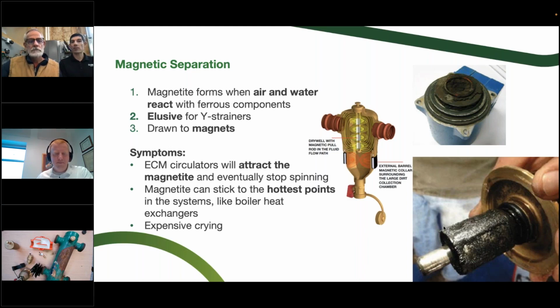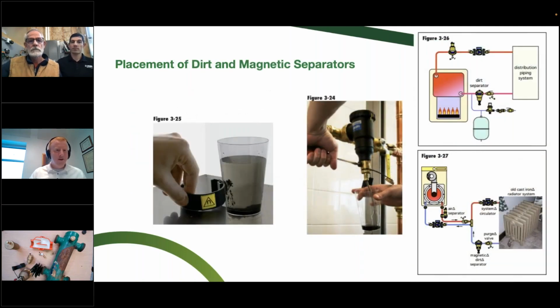So we need to have a better magnet to catch that magnetite first, to protect the pumps and to protect the magnetite from cooking on the hottest points of the system, like a boiler heat exchanger. I think the other thing to think about too is recognizing that it is a magnetite issue. I talk to a lot of contractors where they see a circulator fail. Do they really take it apart to the point where they can figure out that it was magnetite? Oh, heck no, they don't do that. This thing's a piece of junk. They rip it out and put in a new one, and the new one's going to suffer the same fate. So you've got to have a better magnetic separator before it gets to that.